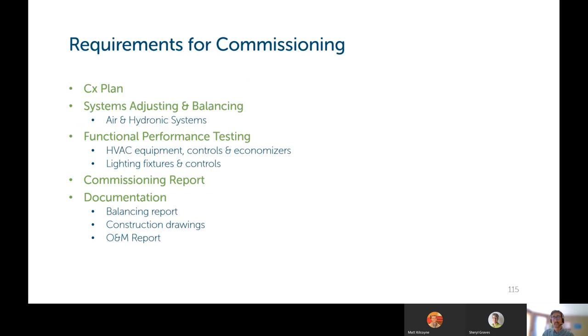Requirements for commissioning: you've got to have a commissioning plan, adjusting and balancing of the air and hydronic systems, functional performance testing of the HVAC equipment, controls and economizers, also the light fixtures and their controls. You need a commissioning report at the end, and with that, some documentation, including the balancing report, any construction drawings and notes on there, and an operation and maintenance report as well.